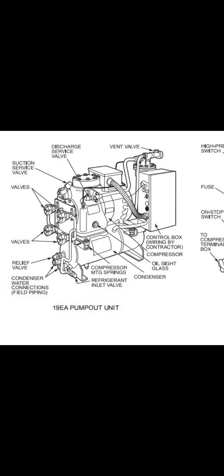So in the plant, one or two storage tanks with a pump down unit must be there, in case you want to remove refrigerant from a chiller. If you have 10, 15, 20 chillers, you need minimum one, but some plants have two storage facilities, storage tank with pump down unit. Some plants I see have permanent piping, and some have flexible. They can make locally made flexible pipe, rolled and secured, so that it reaches all chillers, up to the last chiller.